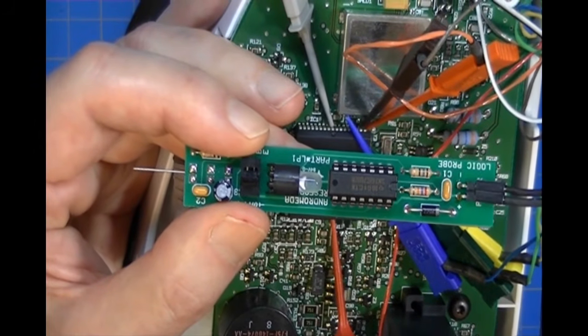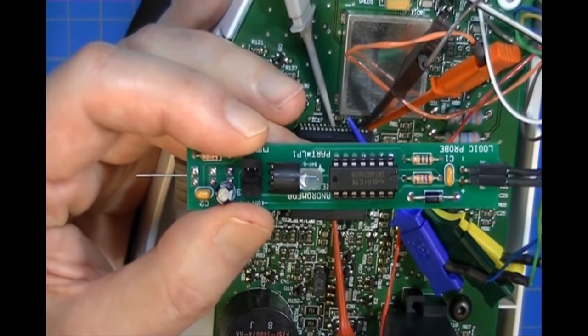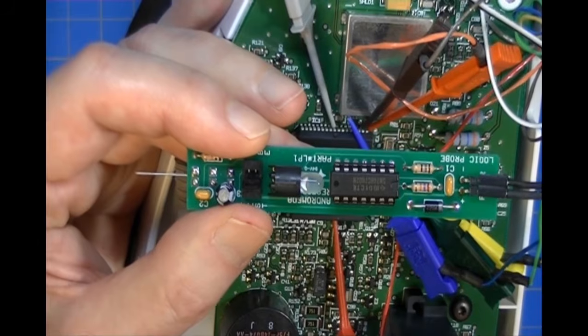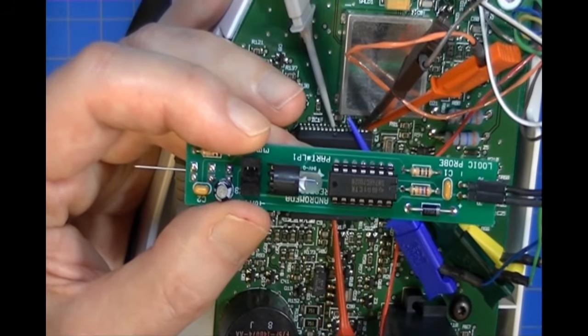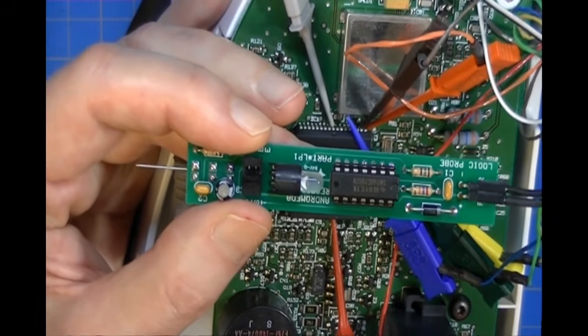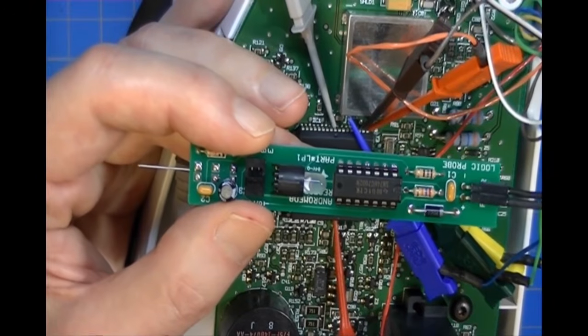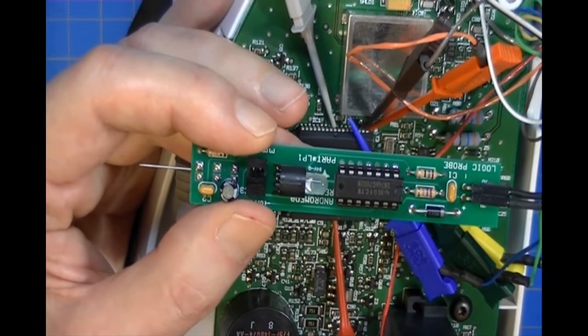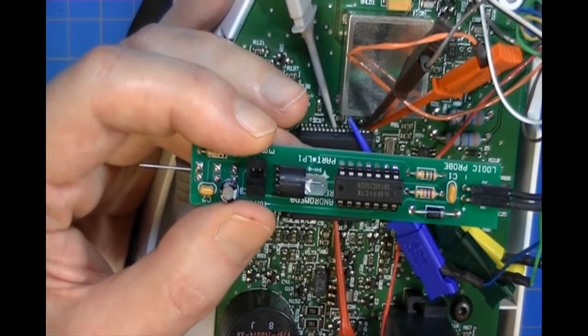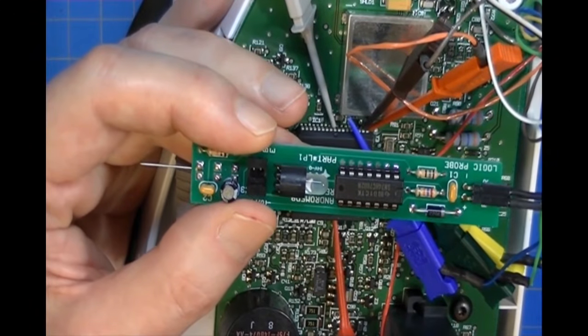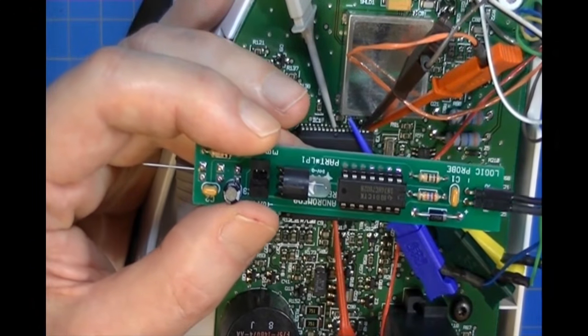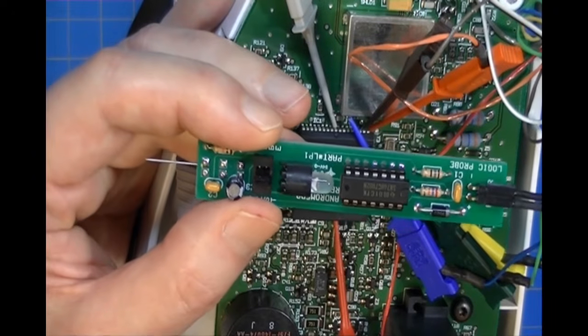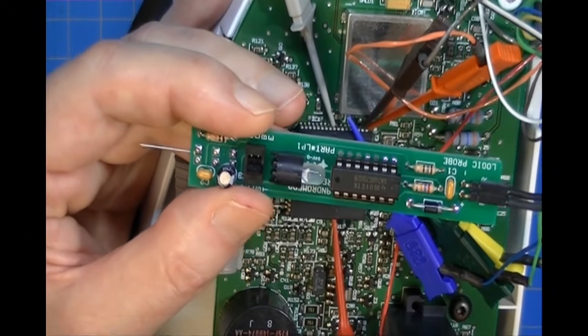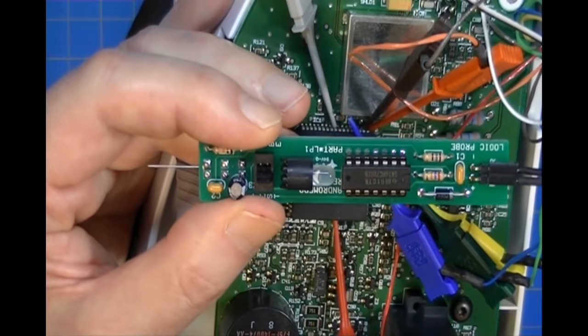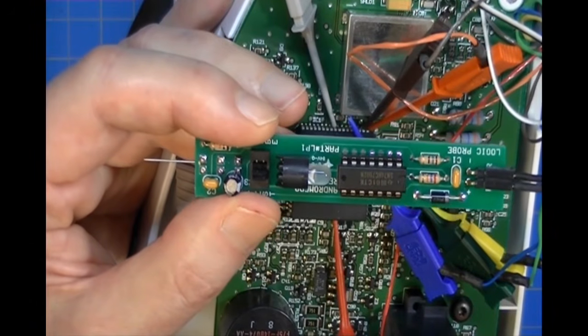It's called test mode, and the other mode is called probe mode. Probe mode sets this to determine logic levels, meaning it's got an LED on it, which shows either a logic 1 or a logic 0. So you can determine, in some cases you won't need to attach a probe depending on what assembly you're working with, if the pin to which a logic level is required is already at the correct level. This probe will allow you to determine that.